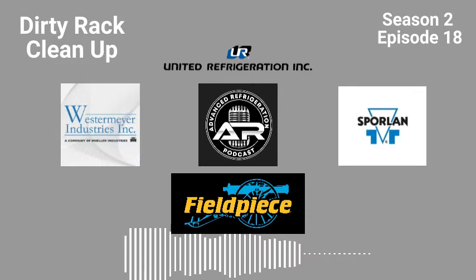Once that's on there, I'm checking my suction filter pressure drops, if they're installed. I'm pretty diligent about that on PMs, making sure I don't have a huge pressure drop in my suction filters, because that will kill a rack. You're making heat, you're not getting that cold suction gas coming back, and with a pressure drop it's inefficient. So make sure those suction filters, if you're leaving them in, have no pressure drop. Otherwise, pull them.